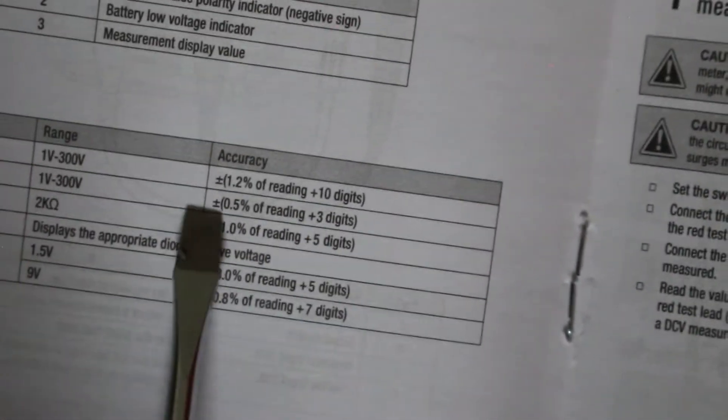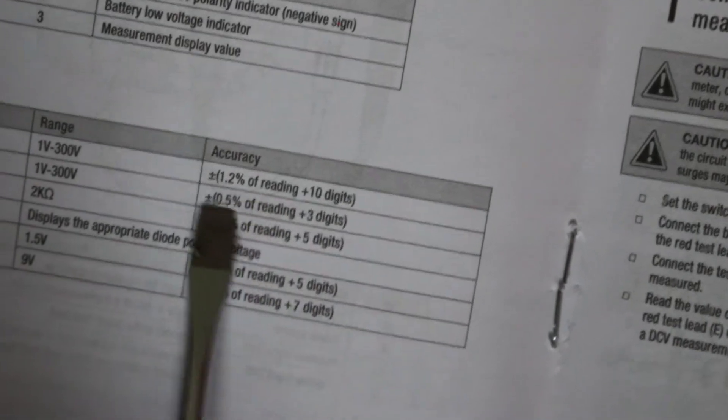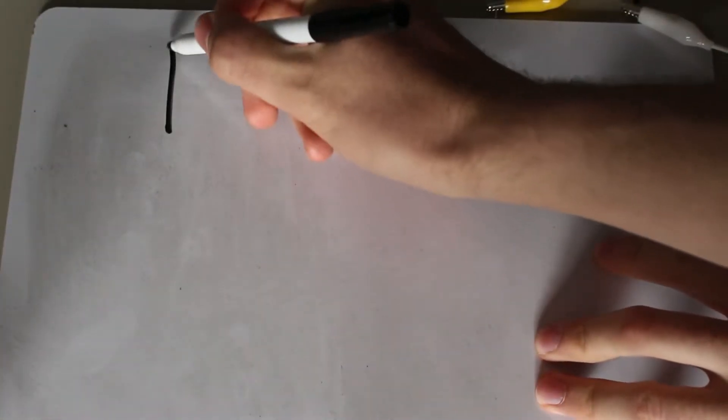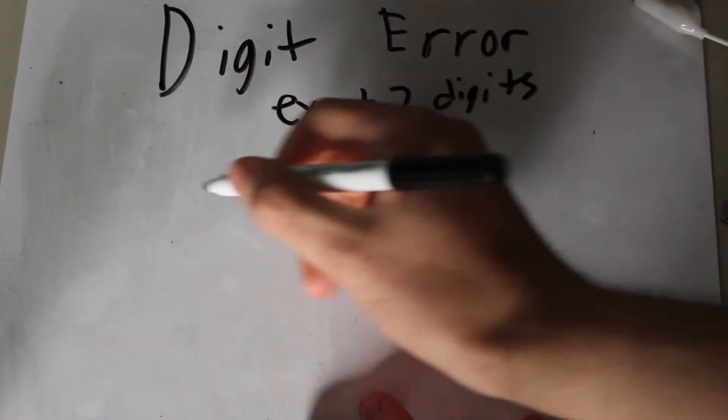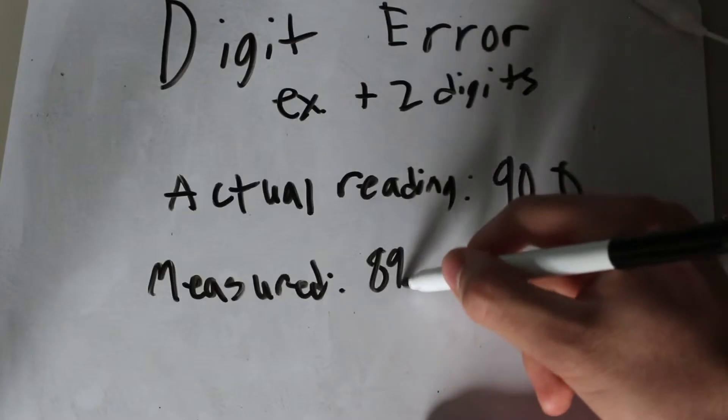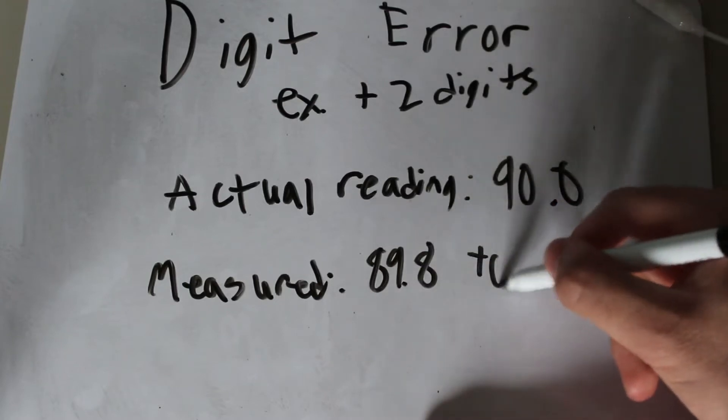Also keep in mind the extra error expressed in digits, which can be found as a plus symbol next to the error. This basically means that the last digit may vary in either direction by at most that many. So a meter with a two digit error could read anywhere from 89.8 to 90.2 from a 90 volt input.